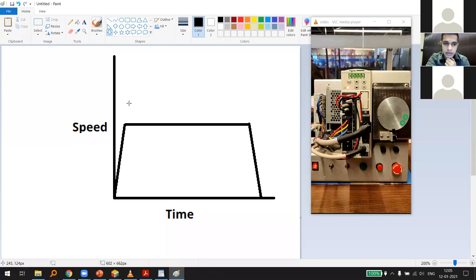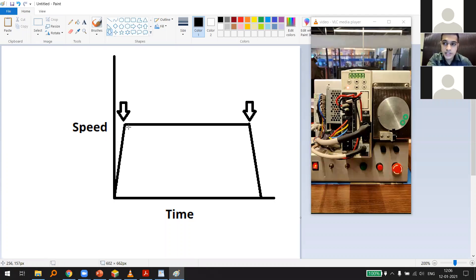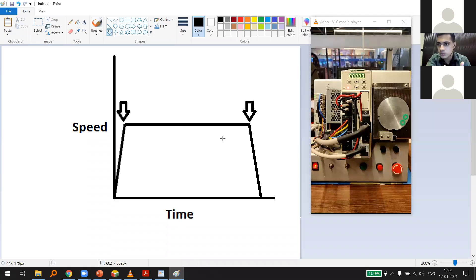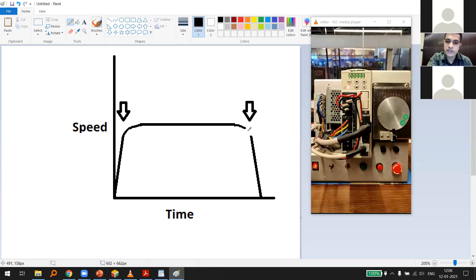These abrupt changes in speed are dangerous when there's a load connected — risk of slippage or position error. To smooth this, we can round the corners of the trapezoid. Modern PLCs and motion controllers have functionality to change the edges of the speed curve, giving a smoother response.